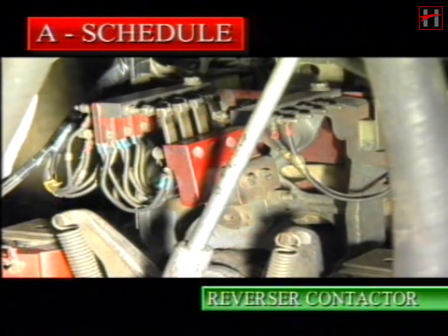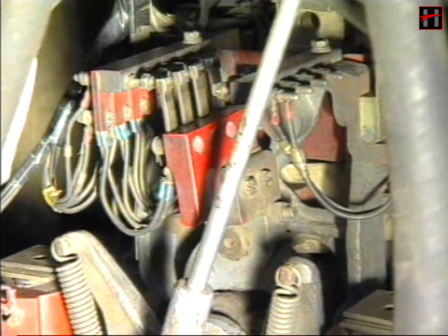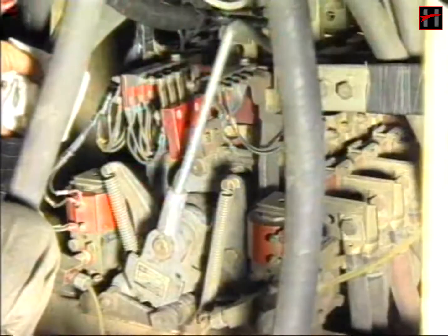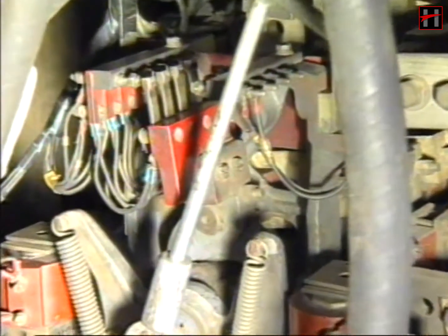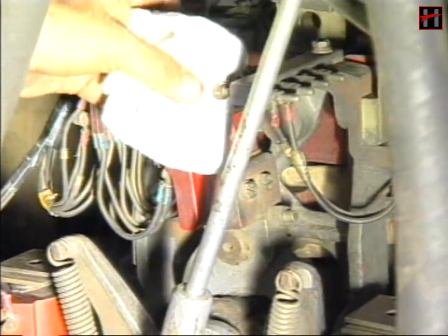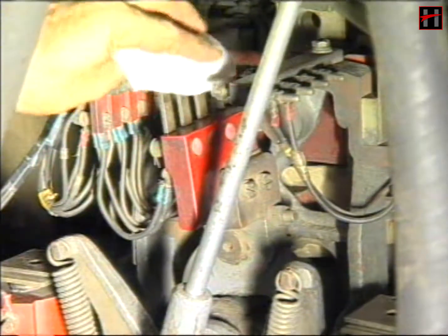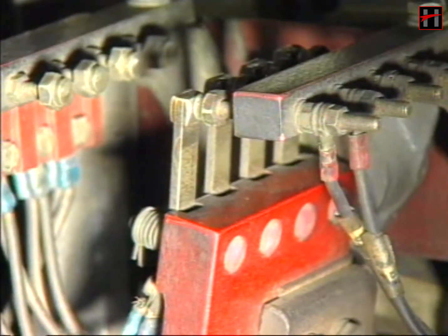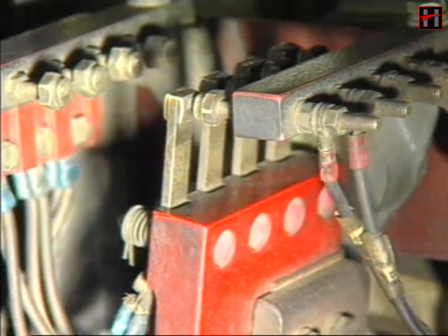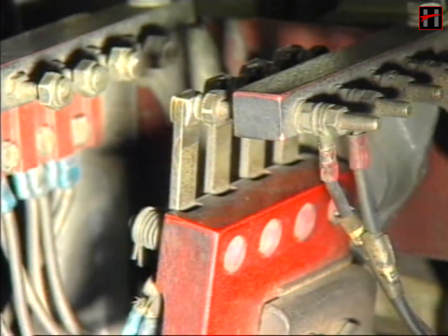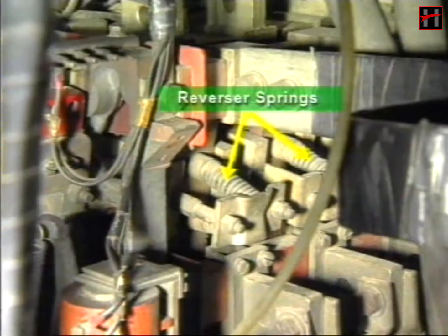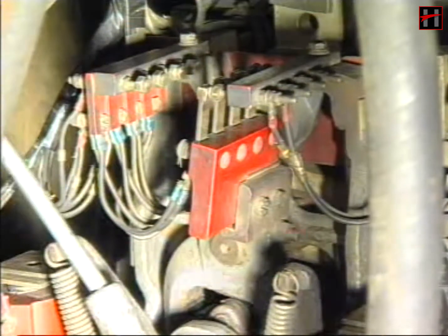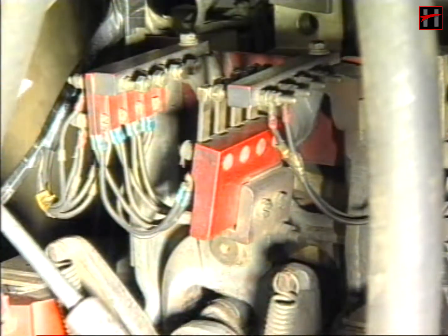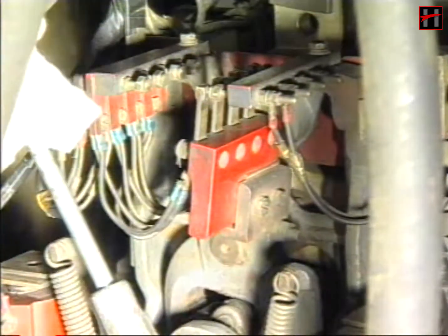In the A schedule of the reverser contactor, check the condition of the contacts of the reverser contactor. If there are signs of overheating or flash marks on the contacts, clean the contacts with lintless cloth or emery paper. Check the alignment and over travel of the interlocks. If over travel has got lost, check the reverser springs and the spring guides of the shunts. Manually check the operation of the reverser contactor. The operation should be smooth.